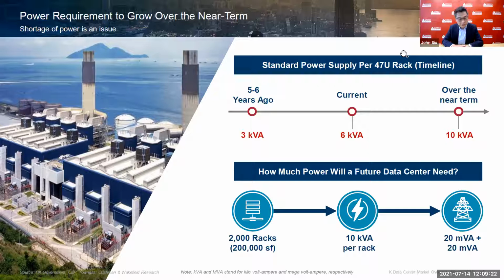If we build a data center with, say, 2,000 racks in a building of 200,000 square feet, and each rack's power capacity is 10 kVA, that means the building has to have 20 MVA plus another 20 MVA - why plus 20 MVA? Because the data center needs a dual source of power as a kind of backup. I can tell you that for a normal industrial building of 200,000 square feet, the power supply capacity is only 3 MVA. That means if a building is converted for data center use, the power has to be 6 times more than the existing use. So that's one of the constraints.